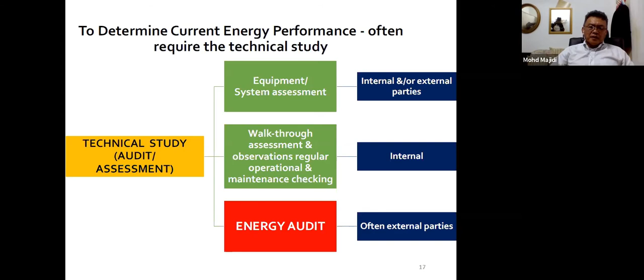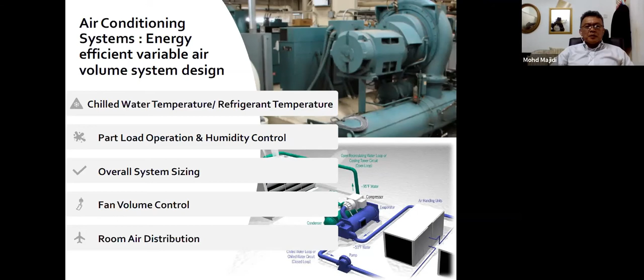Air conditioning, as mentioned earlier, is where up to 60% of your energy is used. Here you can look at chilled water temperatures - a monitoring system will be very useful in addressing this. You look at the opportunity for part load operations and humidity control. Is your system sized properly? Are the fan volumes controlled well? Room air distributions also need to be addressed.